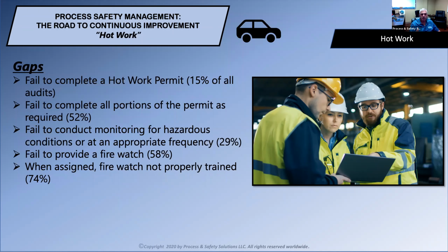Again, we get this information through employee interviews and then actual on-site when we're doing a walkthrough, we may see somebody doing hot work and we'll actually ask them where their permit is. So others are failed to complete all portions of the permit as required. And this is 52% of the time.